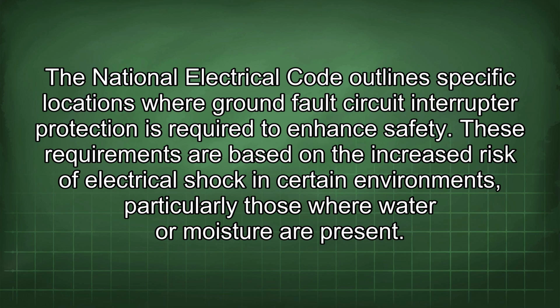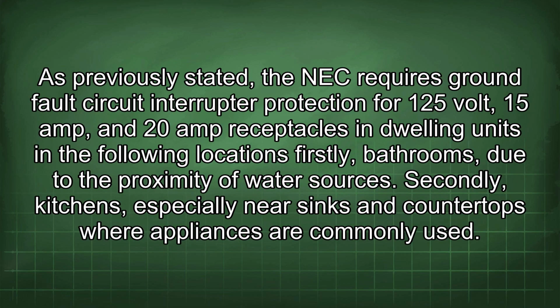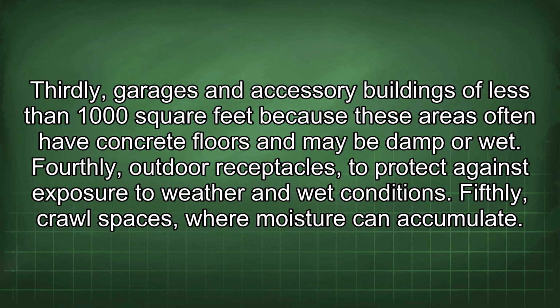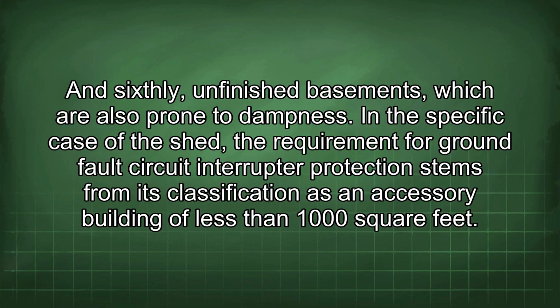These requirements are based on the increased risk of electrical shock in certain environments, particularly those where water or moisture are present. As previously stated, the NEC requires ground fault circuit interrupter protection for 125-volt, 15-amp, and 20-amp receptacles in dwelling units in the following locations. Firstly, bathrooms, due to the proximity of water sources. Secondly, kitchens, especially near sinks and countertops where appliances are commonly used. Thirdly, garages and accessory buildings of less than 1,000 square feet because these areas often have concrete floors and may be damp or wet. Fourthly, outdoor receptacles to protect against exposure to weather and wet conditions. Fifthly, crawl spaces, where moisture can accumulate. And sixthly, unfinished basements, which are also prone to dampness.